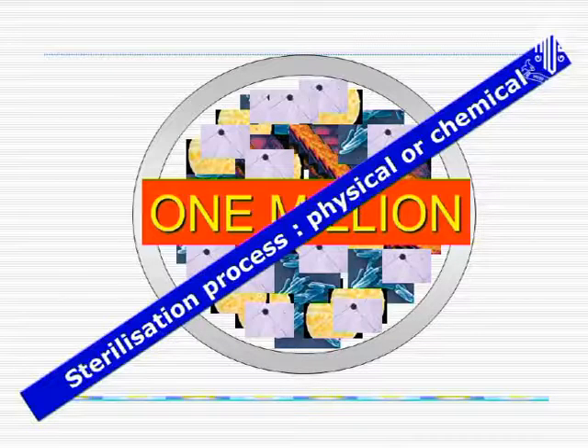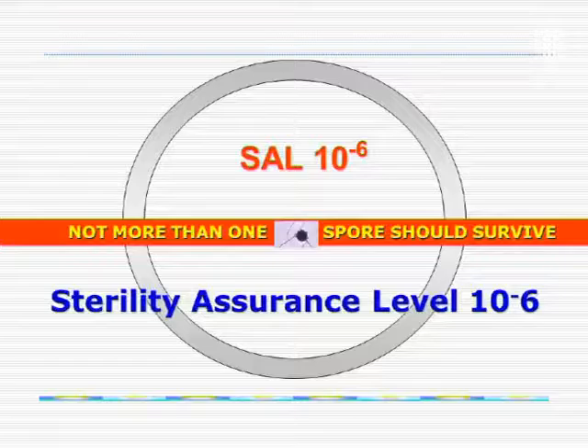It may not be practically possible to remove everything. So we have a sterility assurance level. If you leave one million spores in, the maximum allowed to survive is one — that is, one in one million. That is the standard you should maintain for sterilization, and it is what is needed for ophthalmic practice.